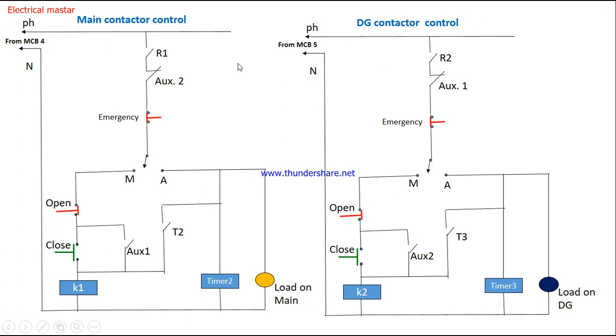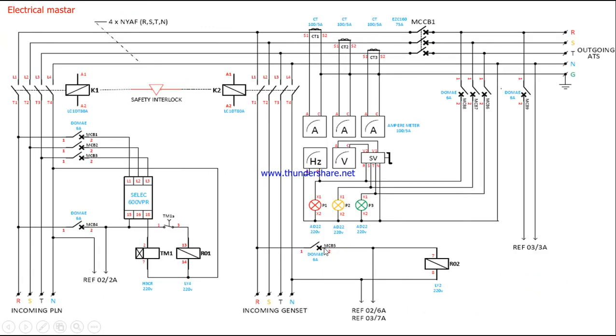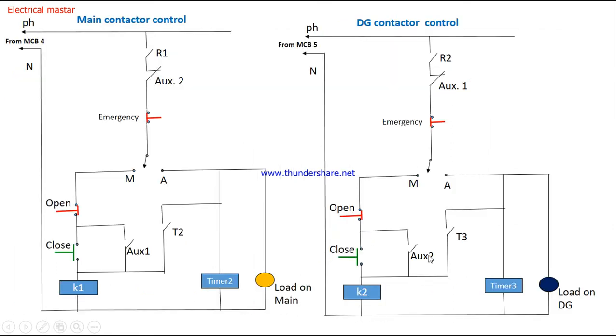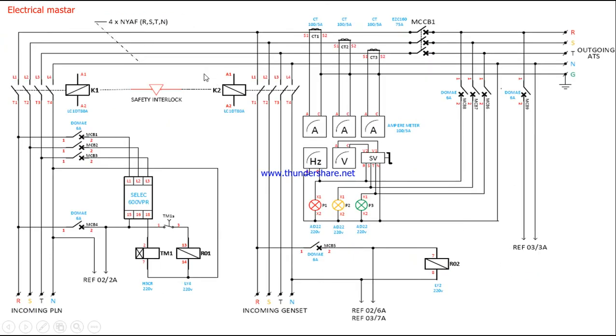For the DG contactor, from MCB5 being closed, R02 is energized and R02 NO closes. It is connected to the NC contact of auxiliary 1 — the interlock for contactor K1 — so K1 must be off before we can close DG contactor K2. From the NC of K1 it goes to the emergency stop push button, then to the manual/auto selector switch. In manual mode, the stop and start push buttons control K2 — pressing start activates K2 and the holding contact closes. In auto mode, timer 3 activates; after its delay, T3 closes and supply extends to K2, which picks up and indicates load on DG.